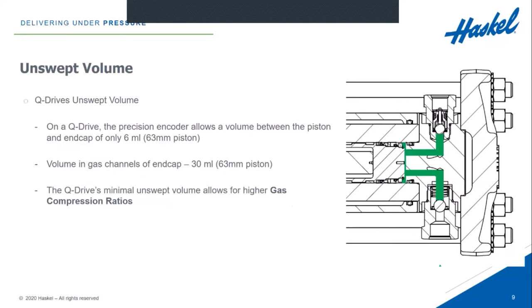In the Q-Drive, a precision encoder very precisely controls the position of the piston. When the Q-Drive starts up and orients itself in the morning when you first power it up, it actually pushes the piston all the way to slightly touch the end cap so the control knows exactly where the piston and the end cap are. While it's actually cycling, it gets very close to the end cap, and on a 63 mm piston there's only six milliliters of unswept volume between the end cap and the end of the piston. The gas channels in the end cap add only 30 milliliters. Because we have such a small unswept volume in the Q-Drive, that allows us to have much higher gas compression ratios than most other boosters or compression systems allow for.